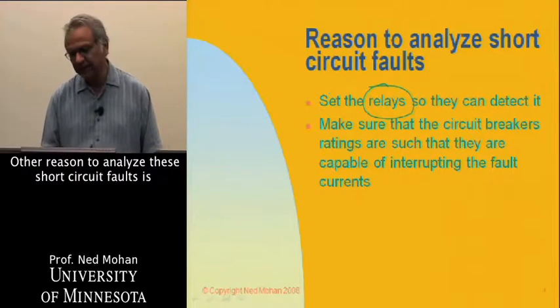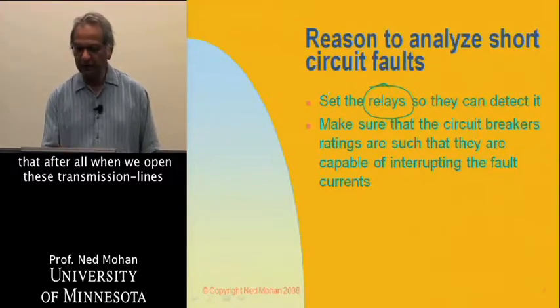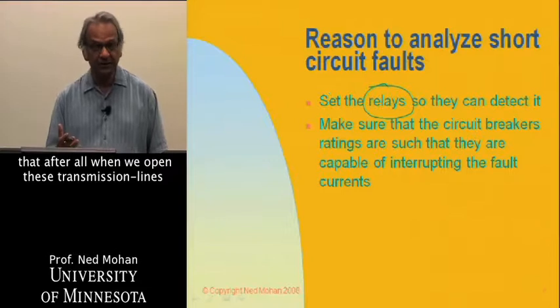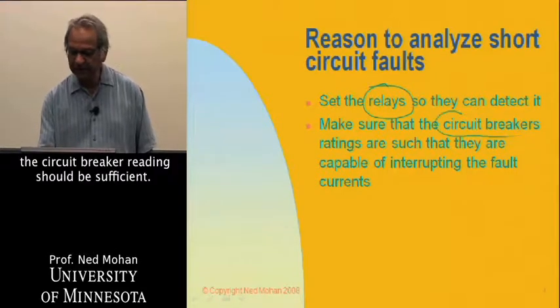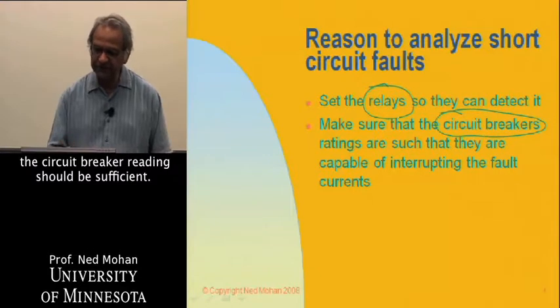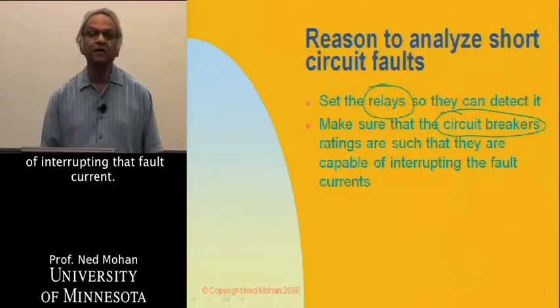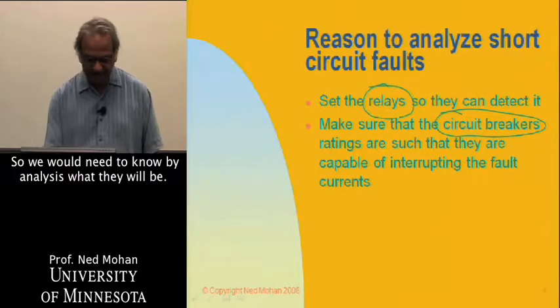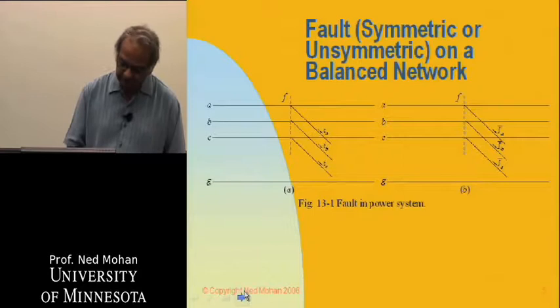Another reason to analyze these short circuit faults is that when we open these transmission lines under faulted conditions using circuit breakers, the circuit breaker rating should be sufficient. The circuit breaker should be capable of interrupting that fault current. So we need to know by analysis what they will be.